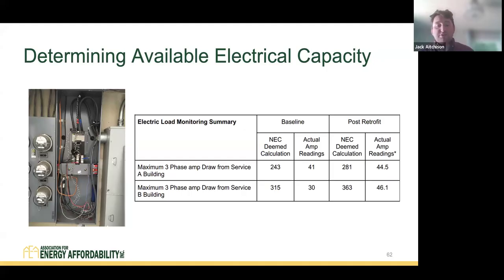And then on the post retrofit, this ties into how efficient these heat pumps are. You can see we saw a slight increase for the calculated load, about 40 to 50 amps for each, but the actual increase measured was only 3.5 amps for building A and only 16 amps for building B. So a significant reduction compared to the calculated load. This is a process that we use all the time in our projects, and technical assistance providers can help you plan for this type of monitoring to avoid costly electrical upgrades. Next slide, please.